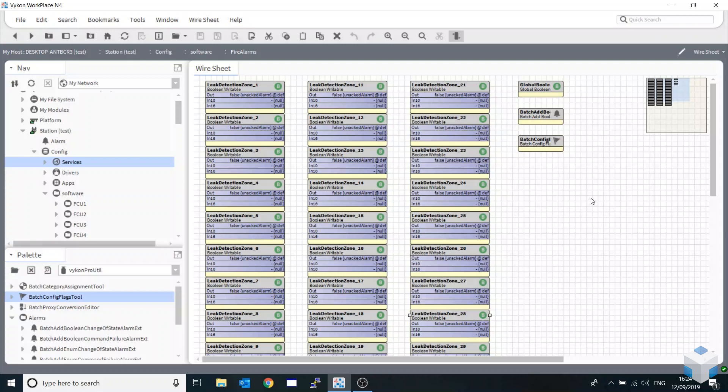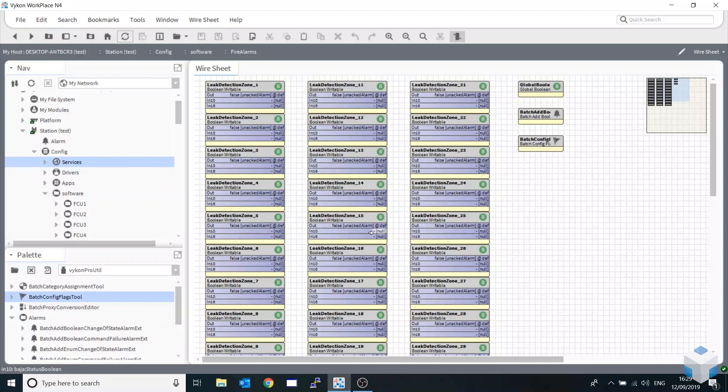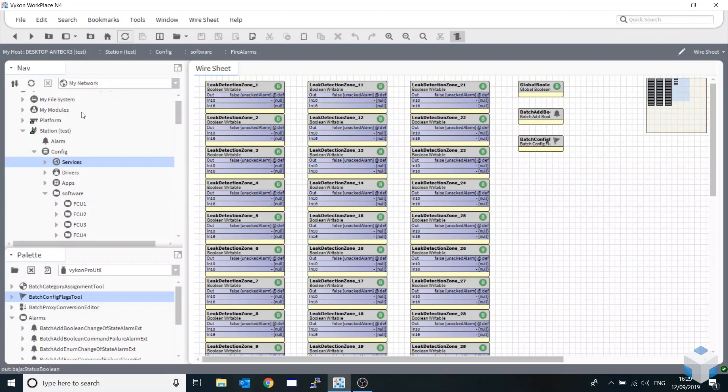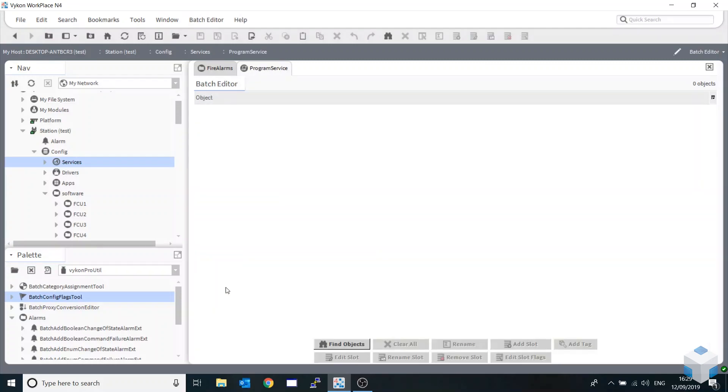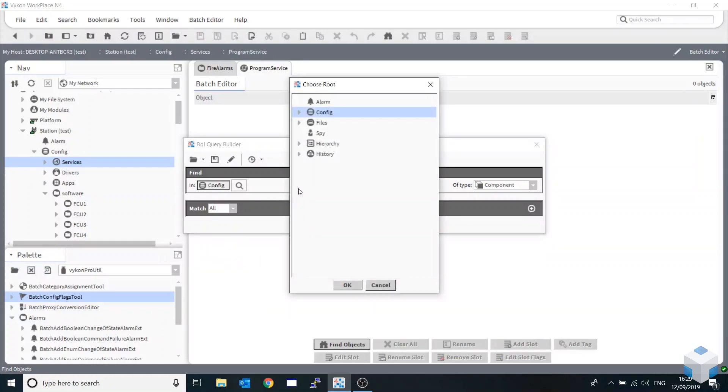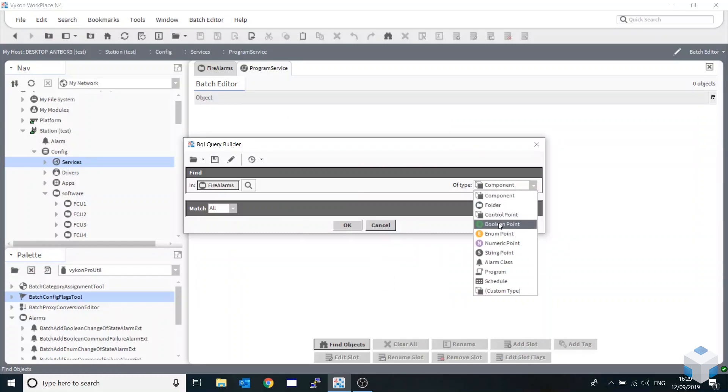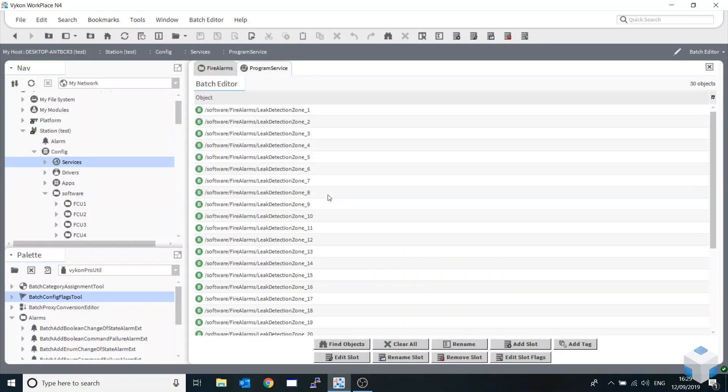We're going to have a couple more sections to this video. Welcome back to the fourth part of our video on how to do mass changes on our system. I'll be looking at the program service. This will be a quick overview - I'll be doing a more in-depth video on how to use program service, but currently I want to show you how to do things quickly on mass, especially at the end of a project. This will show you how we can actually use that to affect things within our blocks across the whole station. Hold down control and double click services to open up another tab. Go into our program service and find objects. Again, on previous videos I showed you how to use the BQL query format. I'm going to go down and point out our fire alarms. I won't have to use a naming convention because I know every point in there I need to change is a boolean point. Hit OK - we've now pulled up all our leak detection zones.